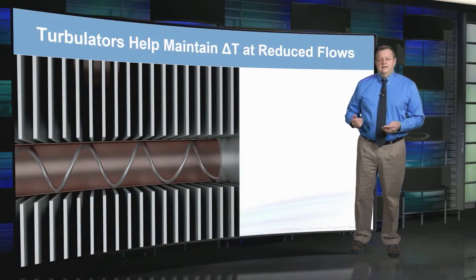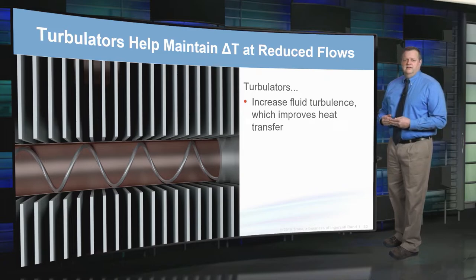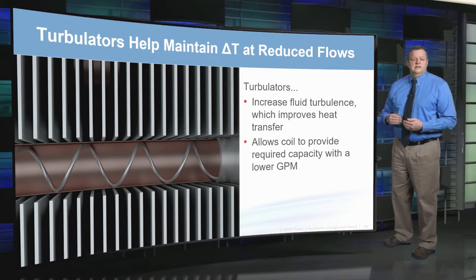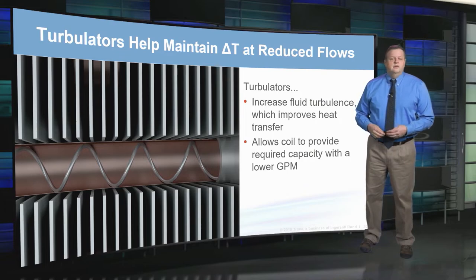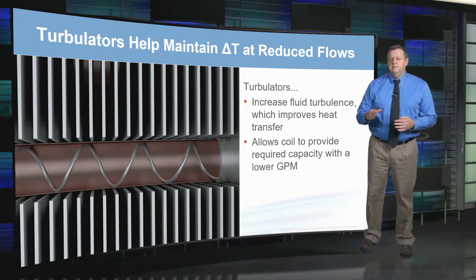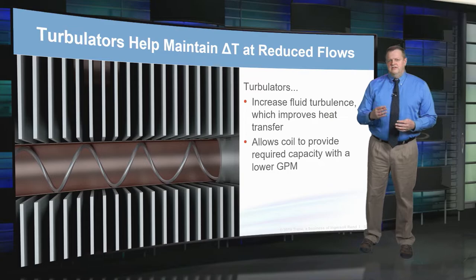Regardless of tube diameter, turbulators allow coils to maintain — and in most cases increase — the delta T at part load. So in selecting coils for higher delta T systems, turbulators are a great option. They increase fluid turbulence, which improves heat transfer, allowing the coil to provide required capacity at lower GPM, leading to reduced pumping energy at part load conditions. Trane has over 50 years of successful field experience with turbulators, with performance certified by AHRI. Now let's talk about water velocity — earlier I eliminated coils with water velocity at design conditions less than 2 feet per second.